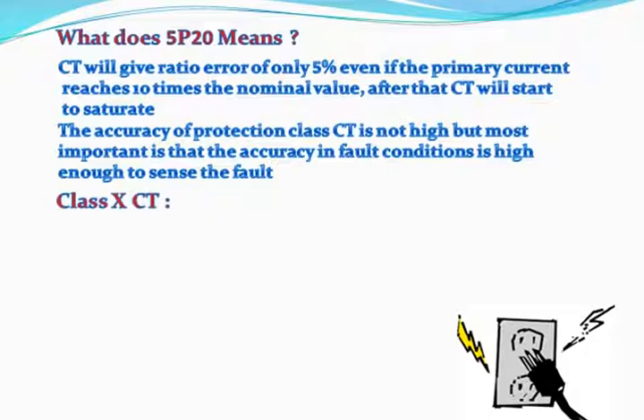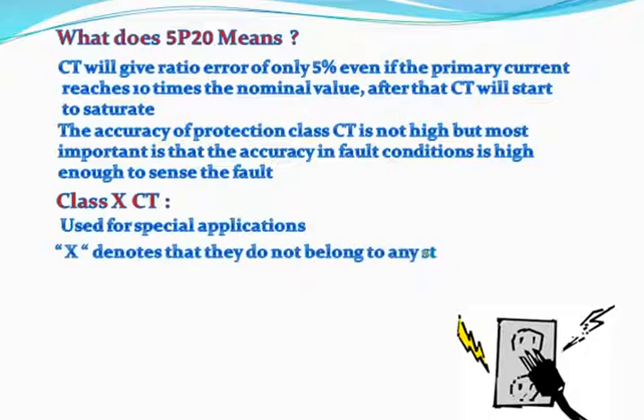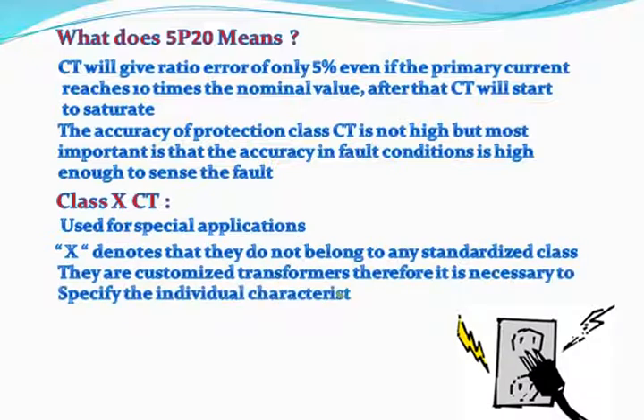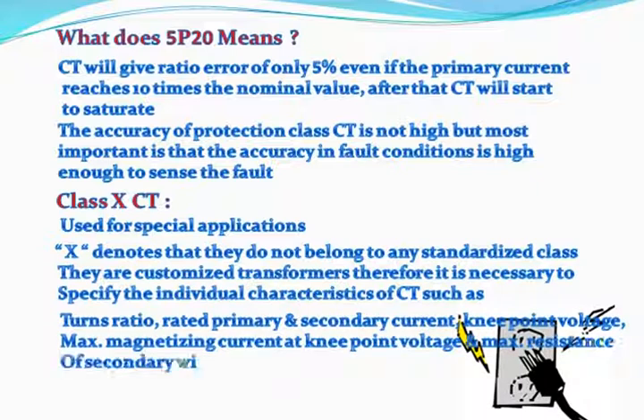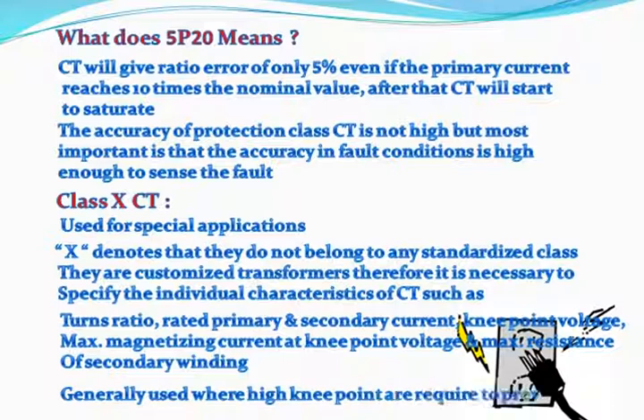Class X CT is used for special applications. X denotes that they do not belong to any standardized class; they are customized transformers. Therefore it is necessary to specify individual characteristics such as turns ratio, rated primary and secondary current, knee point voltage, maximum magnetizing current at knee point voltage, and maximum resistance of the secondary winding. They are generally used where high knee point voltages are required to prevent saturation at high currents.